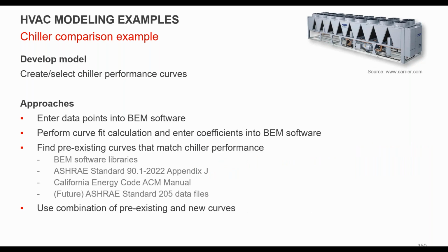So what do you want to do here? What are the steps? Basically you're going to take those data points that you have and translate them into the BEM software that you're using. You might be doing a curve fit to take those data points and turn them into those cubic and bicubic equations to determine the coefficients. With some software, you can just put that data in and it will calculate it for you. You might go grab some pre-existing curves that look similar.